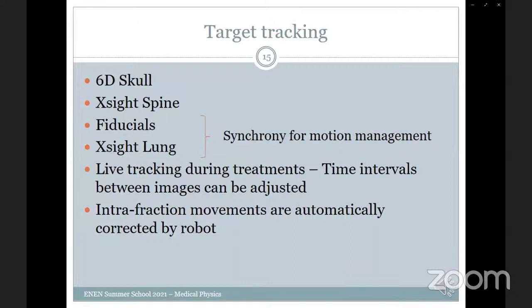For target tracking, we have some types of tracking. The first tracking type is the 6D skull, the second is Xsight spine. We also have fiducial and Xsight lung tracking, which can combine with Synchrony for motion management. It's live tracking during the treatment, so let's say every 45 seconds we are creating a new image pair so we can verify the patient position. The time intervals between images can be adjusted between 20 seconds and 2 minutes, depending on the stability of the patient. And when we see patient movements, setup errors, we immediately send this information to the robot and it's corrected automatically.